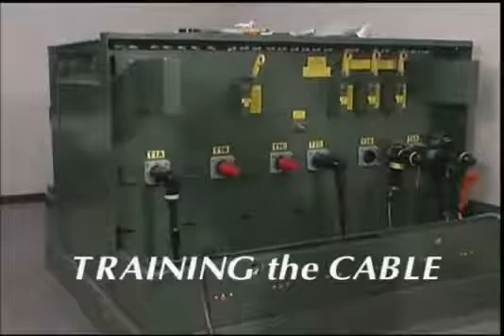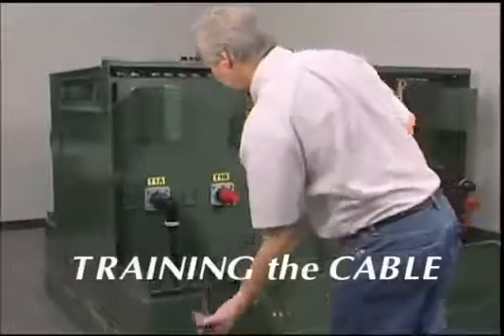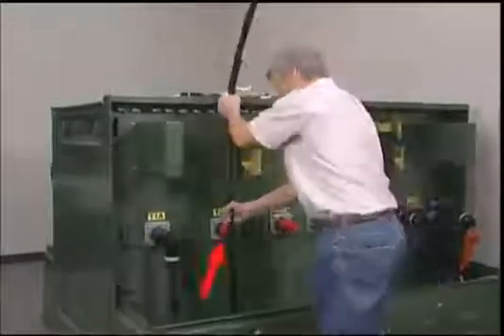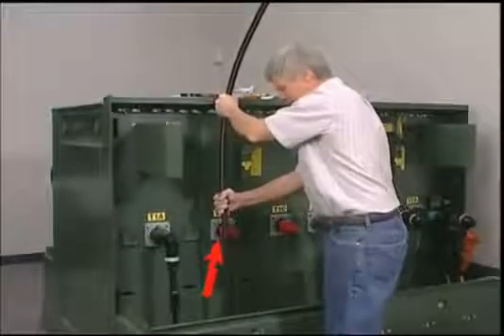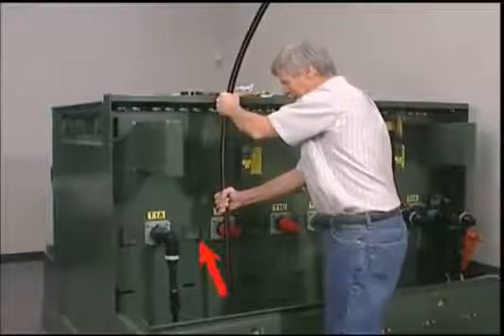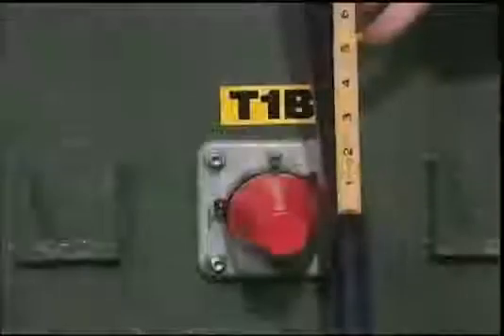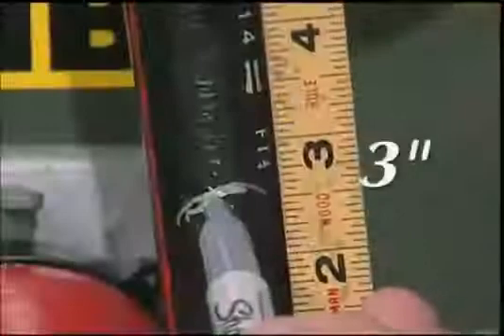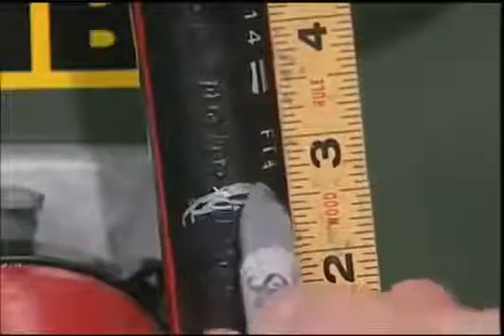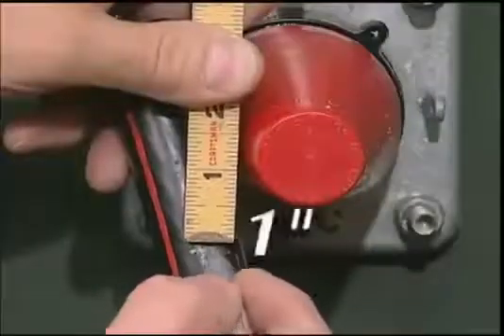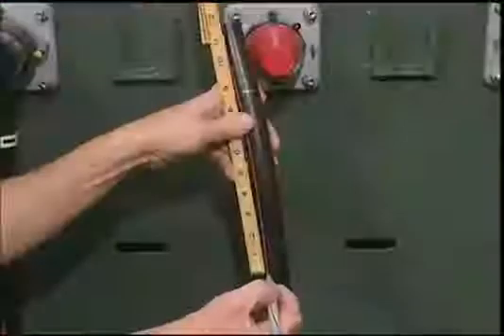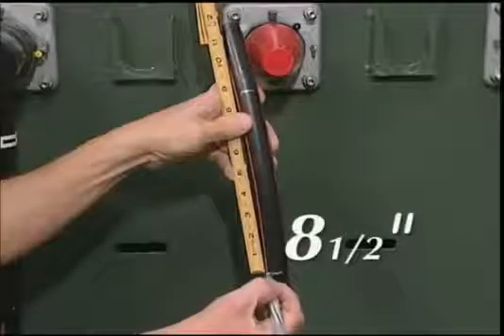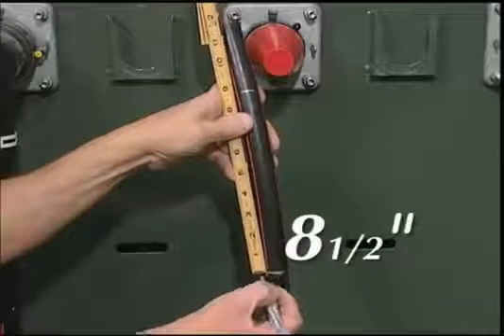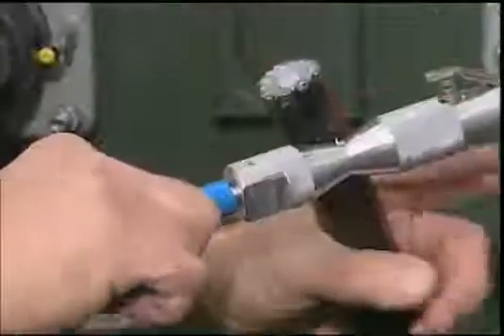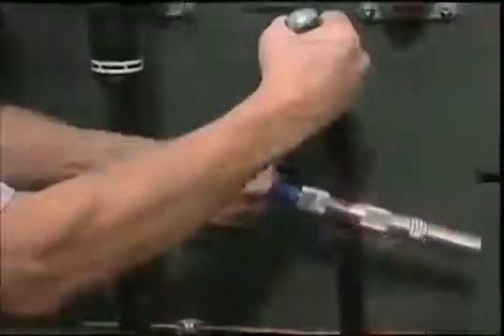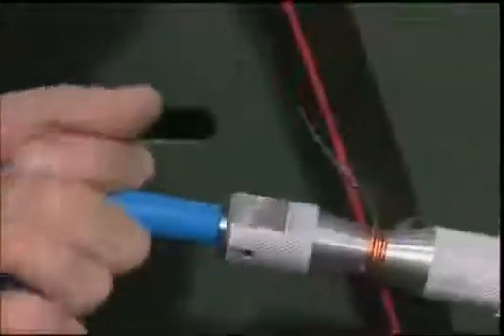The first task is to train the cable, making sure there are no bends. You'll want it lined up with the bushing and the adjacent parking pocket to allow proper operation. Mark the cable at least 3 inches above the center of the bushing insert. Mark the cable 1 inch below the center of the bushing. Next, mark the cable again, 8 1/2 inches below your first mark. Then remove the cable jacket to the bottom mark.